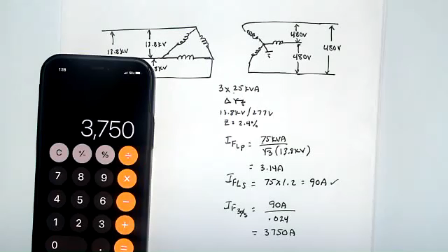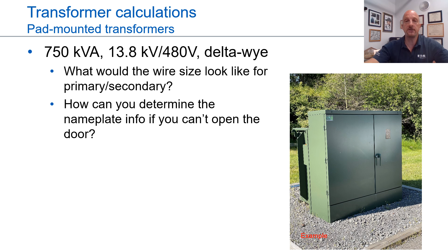So this transformer is 750 kVA, delta Y 13.8 kV to 480 volt. Now, what's unique about these pad-mounted transformers that you might find out in front of a building just like the one I'm in today here is that you can't really tell a lot of times what size they are, and you don't usually get to access the nameplate because the nameplate might be behind one of those 2 doors. So you might have to rely on numbers that are on the outside of the transformer, but most likely you want to talk to the utility company and get that information from them, especially as it relates to impedance and kVA size. So if you have a pad-mounted transformer like this one, how do we know what the ratings are for it? As I mentioned, you can't get inside the door.